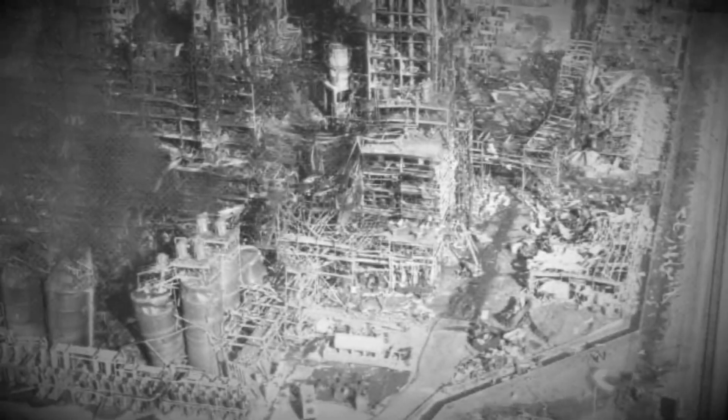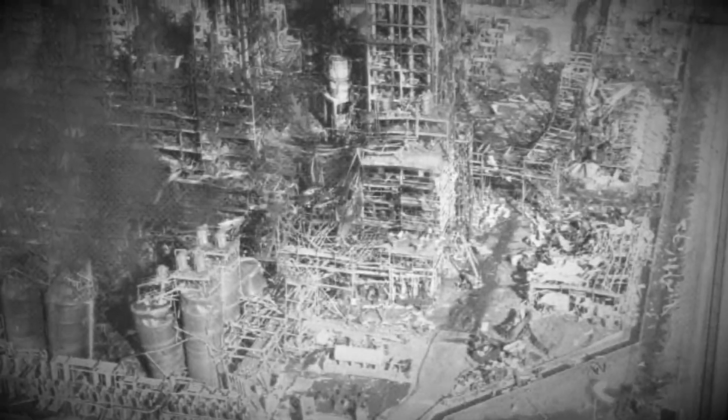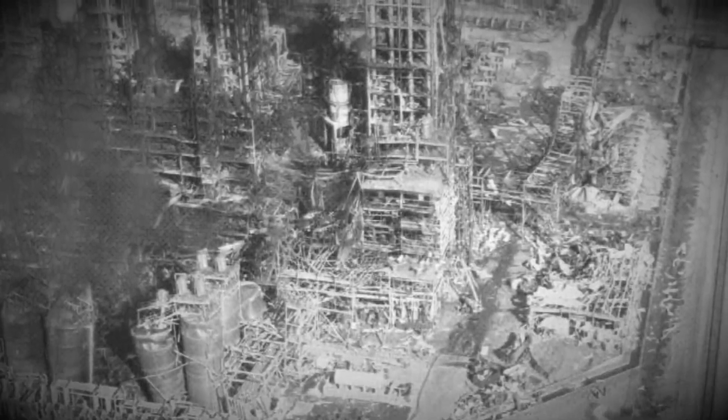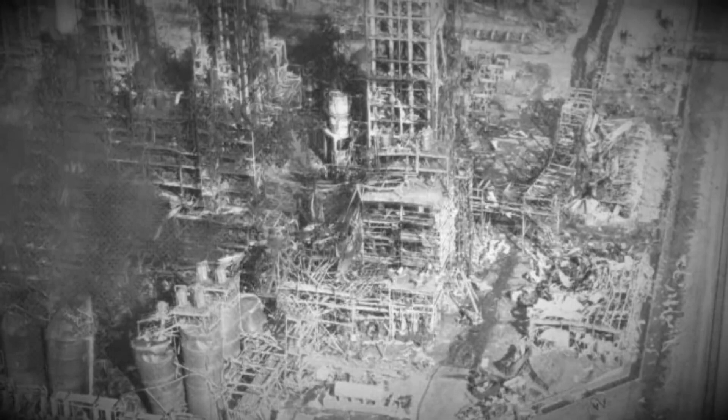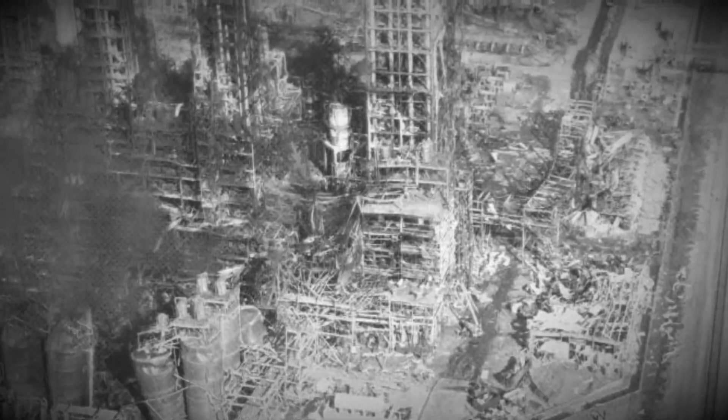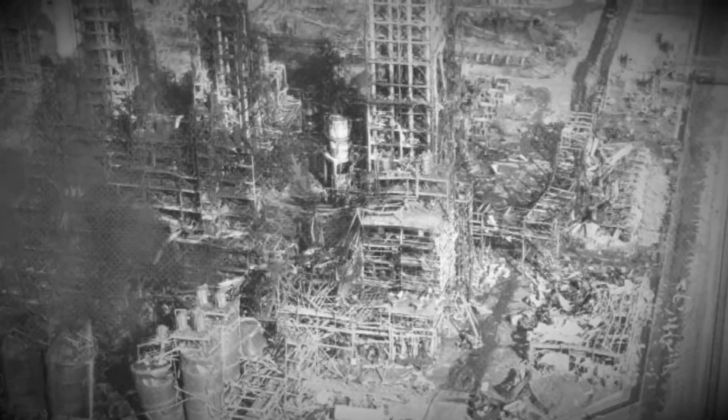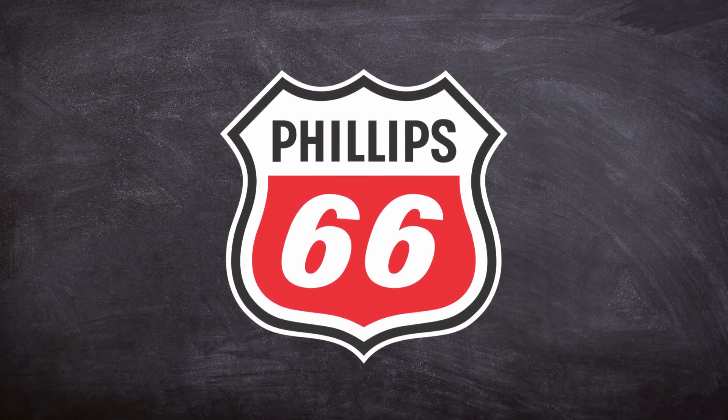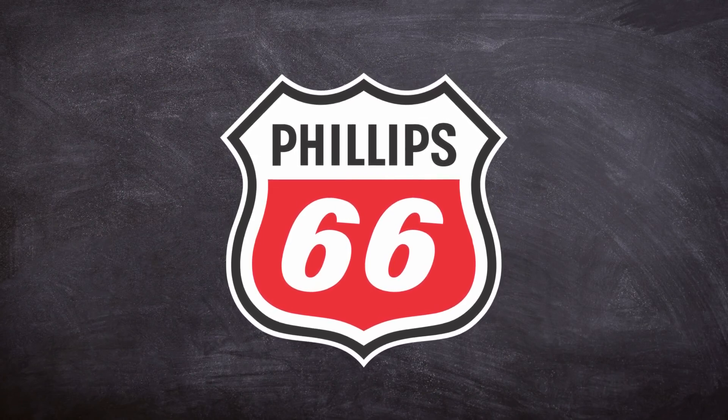Furthermore, there was an on-site lack of combustible gas detection and alarm system which didn't give workers warning of an impending incident. Also, it was found that the fire was helped by the presence of ignition sources and inadequate ventilation systems for nearby buildings.